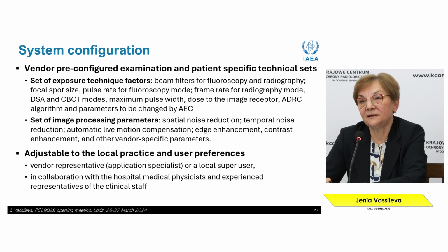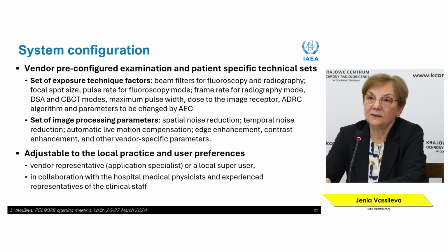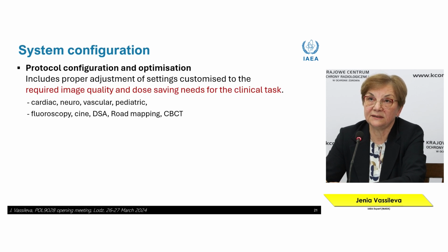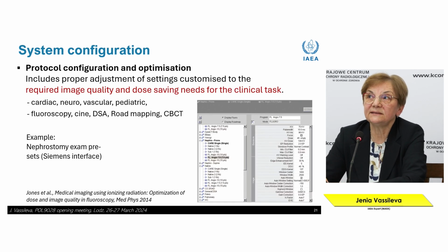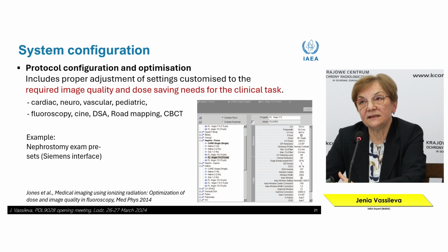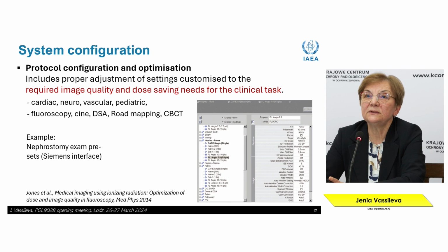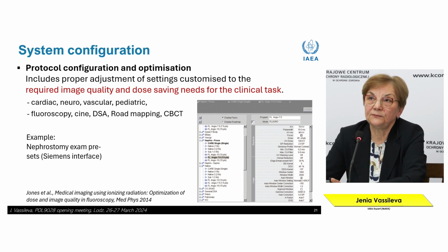They are present during the acceptance. They are responsible for the commissioning, and they are, in fact, the specialists who know the equipment in the best way and can help optimize the practice. So protocol configuration and optimization has an important role.